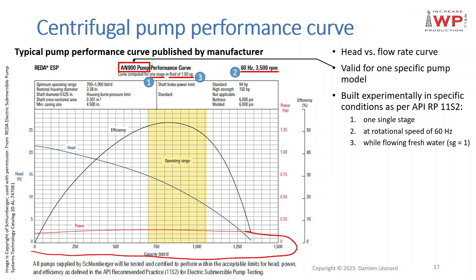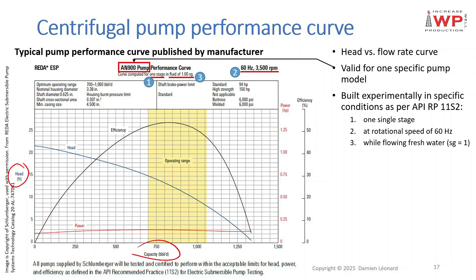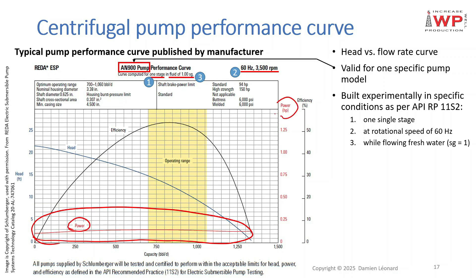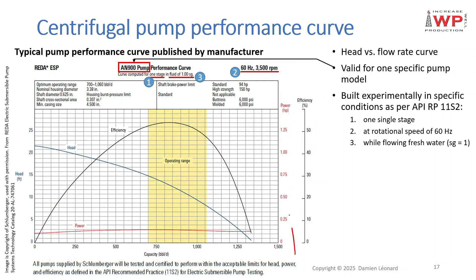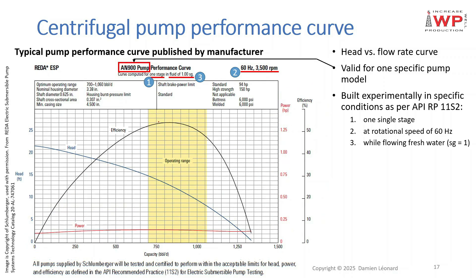On the x-axis you will find the flow rates, and you have three different curves. The most important one, shown in blue, relates to the y-axis and shows the evolution of head with liquid rates. The red curve shows the evolution of power in horsepower. The black curve shows pump efficiency, which reaches a maximum at a certain liquid rate.